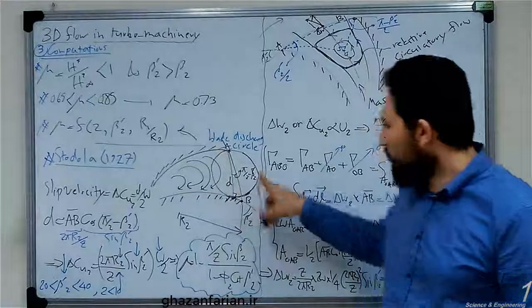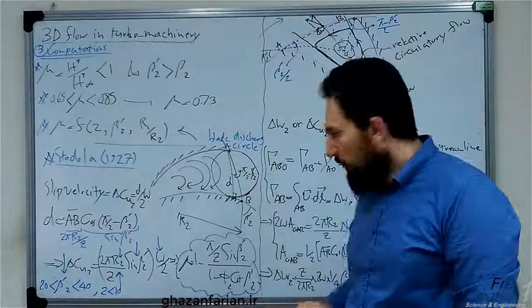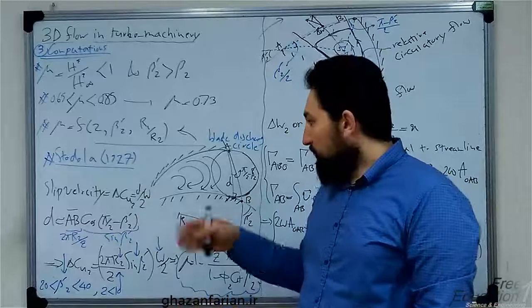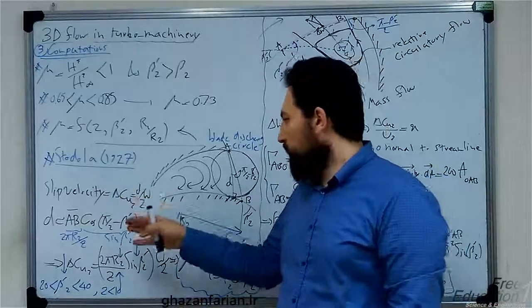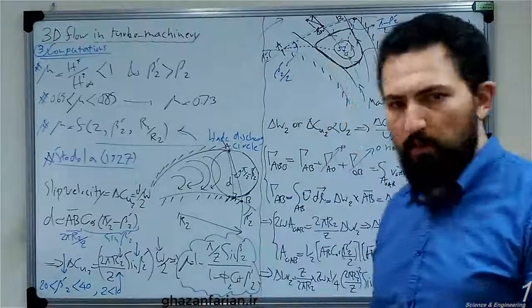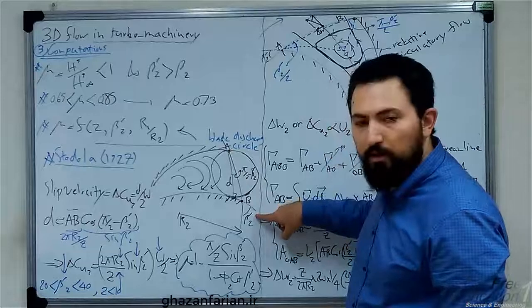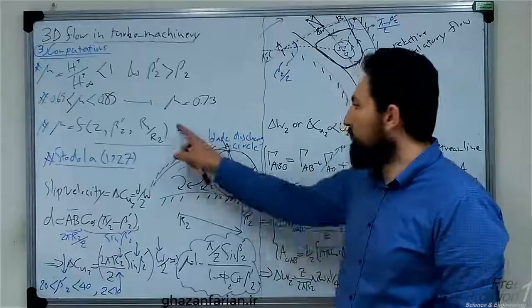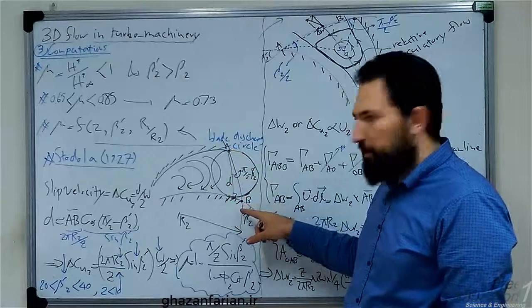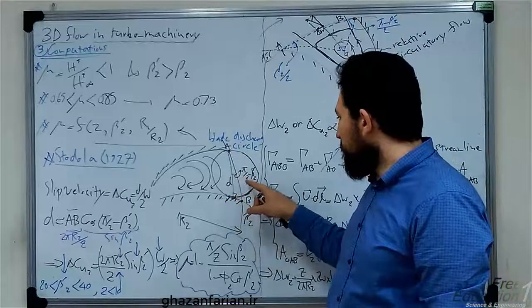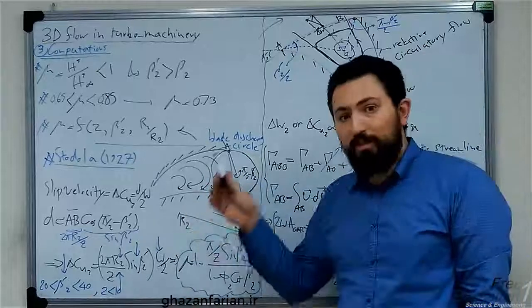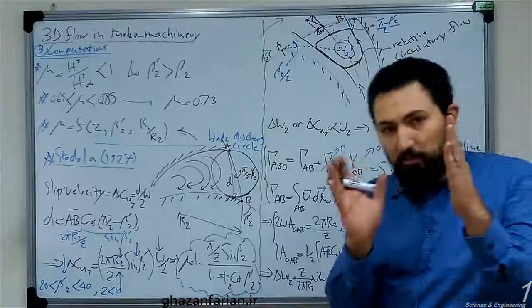There is a circle at the outlet of the blade — the discharge circle — with diameter d and radius d over 2. The slip velocity is equal to the product of the radius of this circle and the angular velocity of the pump. The angle of the blades at the outlet based on the direction of rotation is beta prime sub 2. We have a triangle here with a 90-degree angle, so the other angle is pi over 2 minus beta prime sub 2. This is the direction of rotation of the relative eddy inside the spacing between two blades.